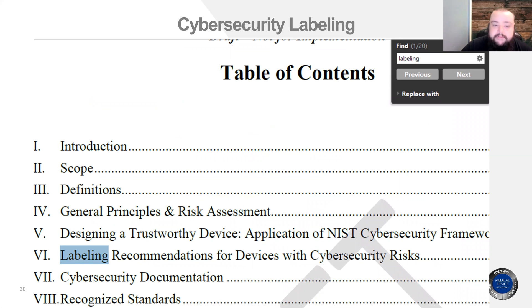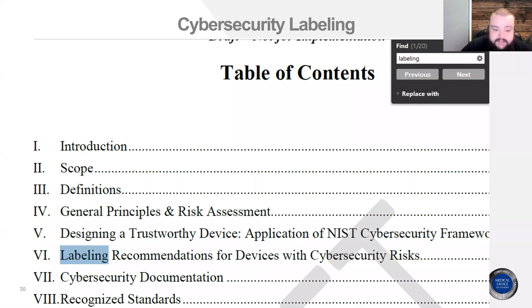For the draft guidance, compared to the current one, labeling is mentioned a total of 20 times. Not only is it included in this revision of the guidance, it has a dedicated section for labeling recommendations, and it gives you acceptance criteria. This is for devices with cybersecurity risks.